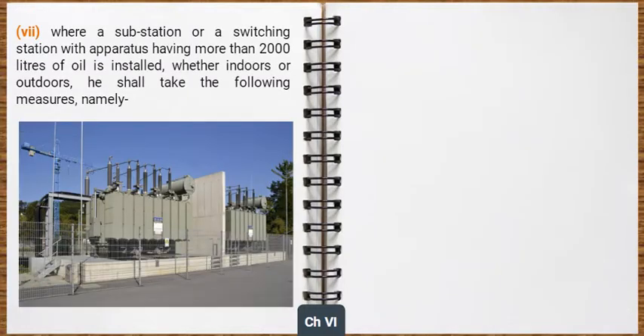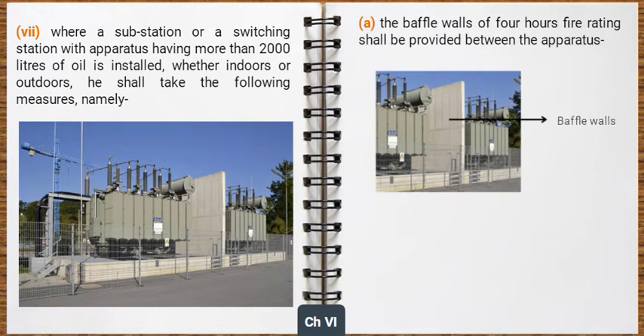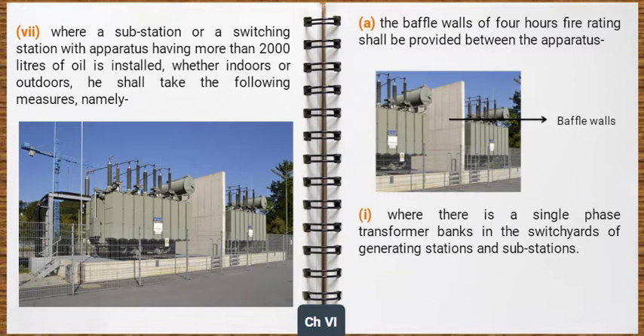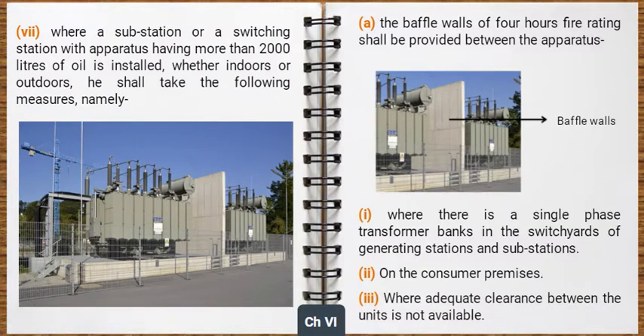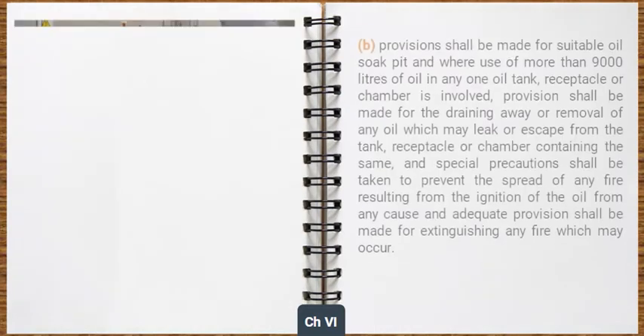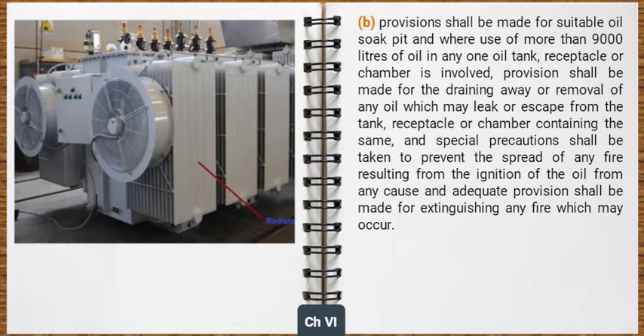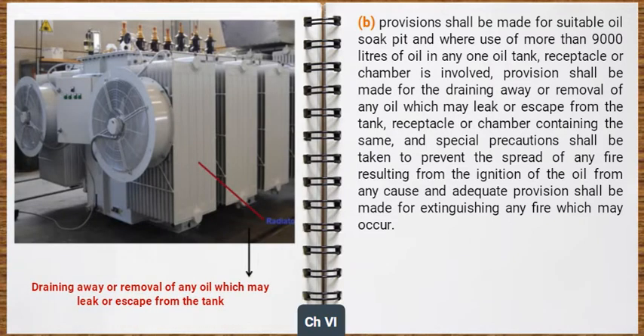Where a substation or a switching station with apparatus having more than 2000 liters of oil is installed, whether indoors or outdoors, he shall take the following measures, namely: baffle walls of 4 hours fire rating shall be provided between the apparatus, where there are single-phase transformer banks in the switch yards of generating stations and substations.